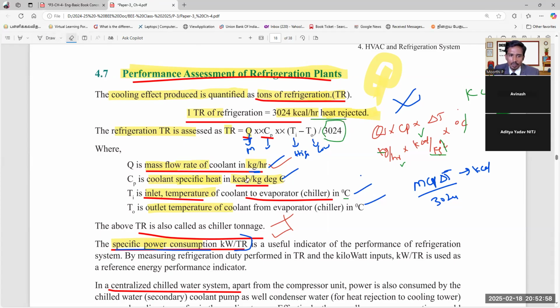Divided by 3024. So Cp is the coolant or specific heat, kcal per kg degree Celsius. Ti is the inlet temperature, the coolant or chiller input, that is the input chiller. Then outlet temperature means the coolant from evaporator output, the chiller output, the outlet temperature.